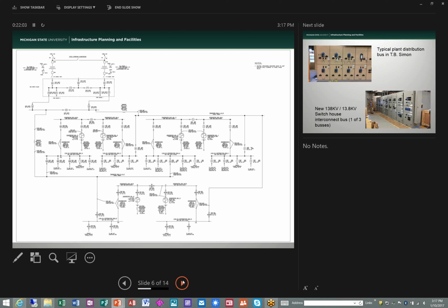Each distribution bus, we've got 6, so 3 pairs are connected to 2 different transfer buses, transfer bus 135 and 246, and those in turn are connected together at an interconnection bus to tie everything together. So we've got a lot of flexibility. There's basically 2 connections to each distribution bus. We can have generators off and close a generator tie bus and backfeed wherever we want to. So a lot of flexibility in this setup. It's easily expandable.